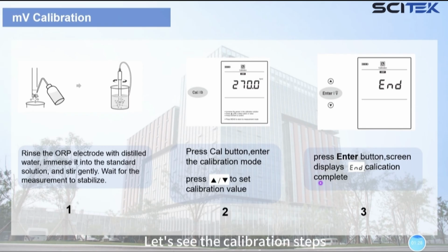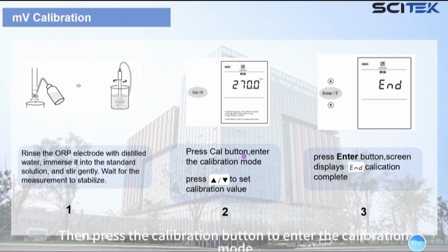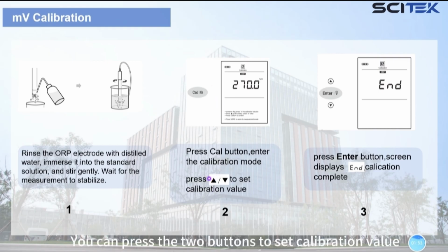Let's see the calibration steps. First, rinse the ORP electrode with distilled water. Immerse it into the standard solution and stir gently. Wait for the measurement to stabilize. Then press the calibration button to enter the calibration mode. You can press the two buttons to set the calibration value. Finally, press the Enter button to confirm. The screen will display the end icon. Calibration completed.